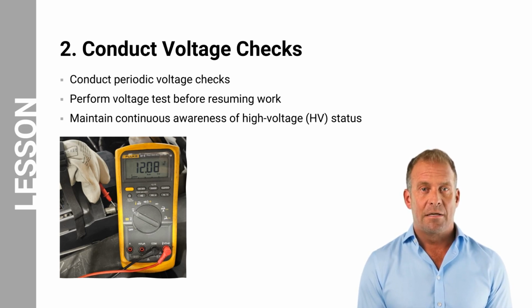Maintain continuous awareness of the high-voltage system status throughout the work. If you suspect the system has become energized at any point, immediately stop work and retest for voltage. Encourage a safety-conscious culture and make it a standard practice for everyone involved to monitor and verify the de-energized status of the high-voltage system.